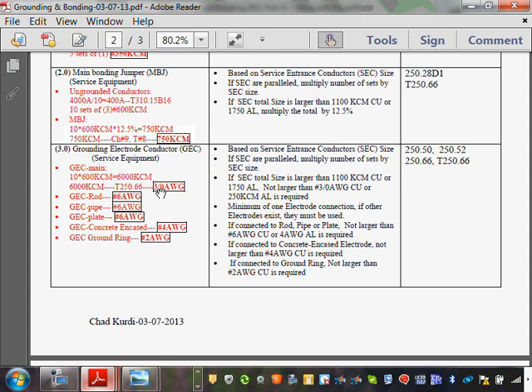If you're bringing the feeder to your house, you only want one set, one conduit coming to your house. So you multiply that number by 1, and it will be the same number. If you have 12 sets, you multiply by 12. Then you take it to 250.66 and get 3 aught. That's the one that's going to the bar. Now, the grounding electrode conductor that's going directly to the rod, remember, there's one coming to the bar and one from the bar going to the rod.